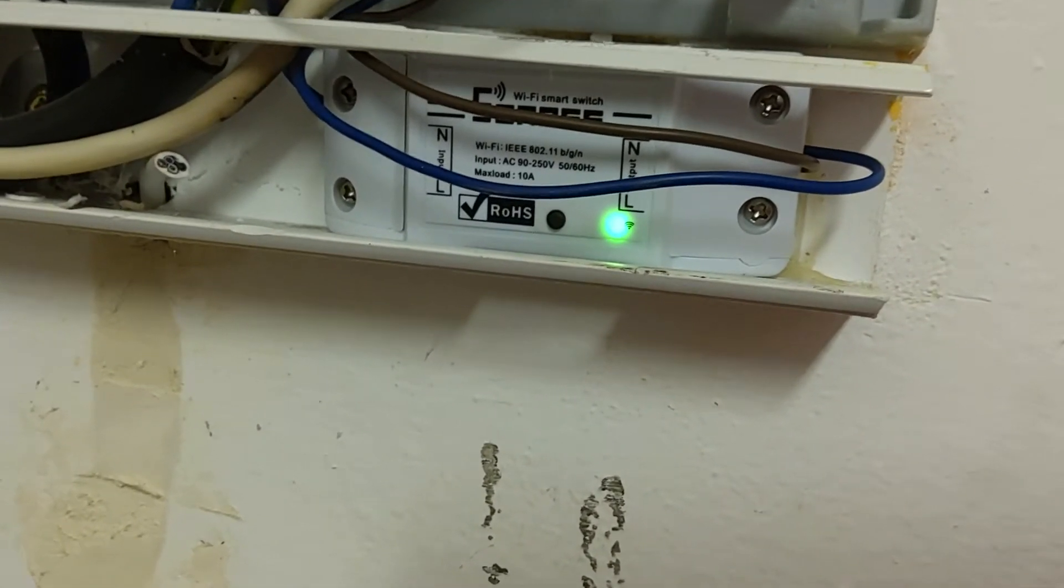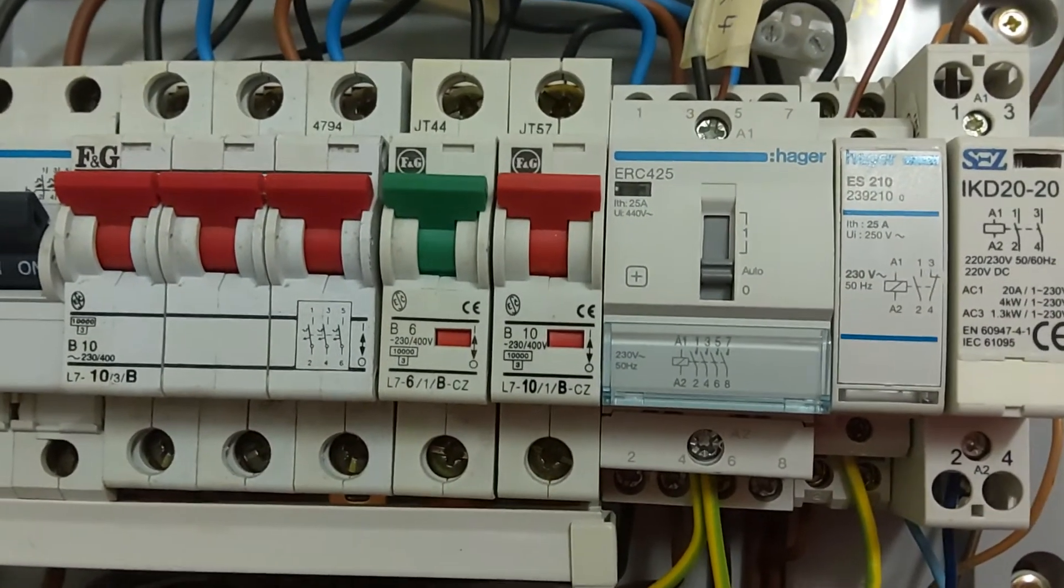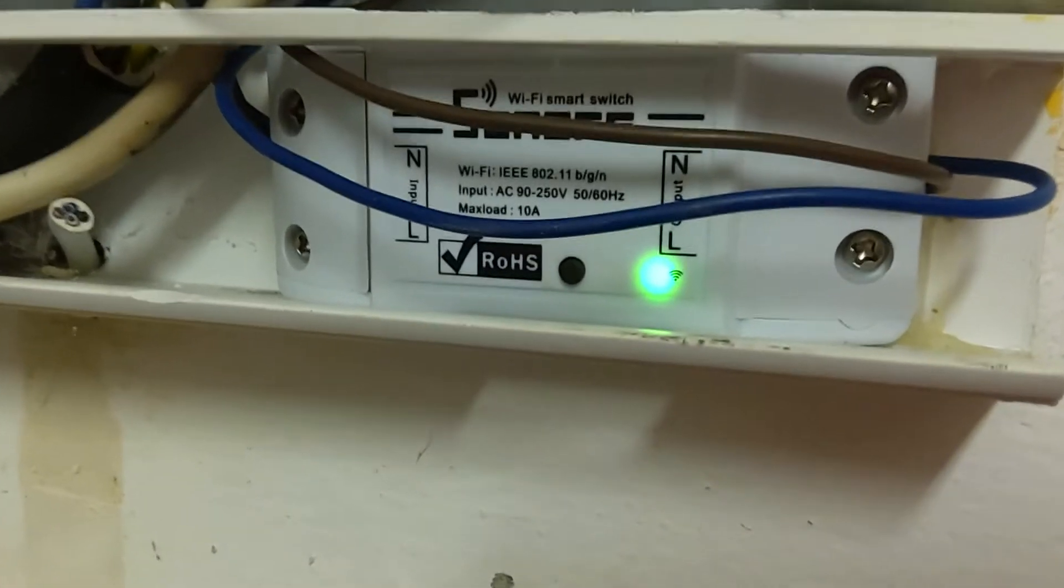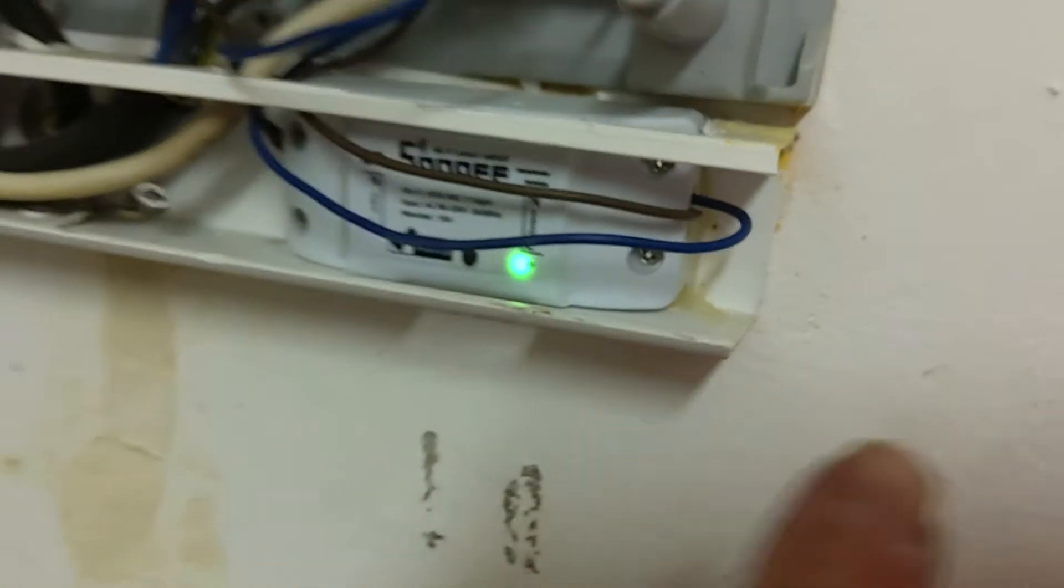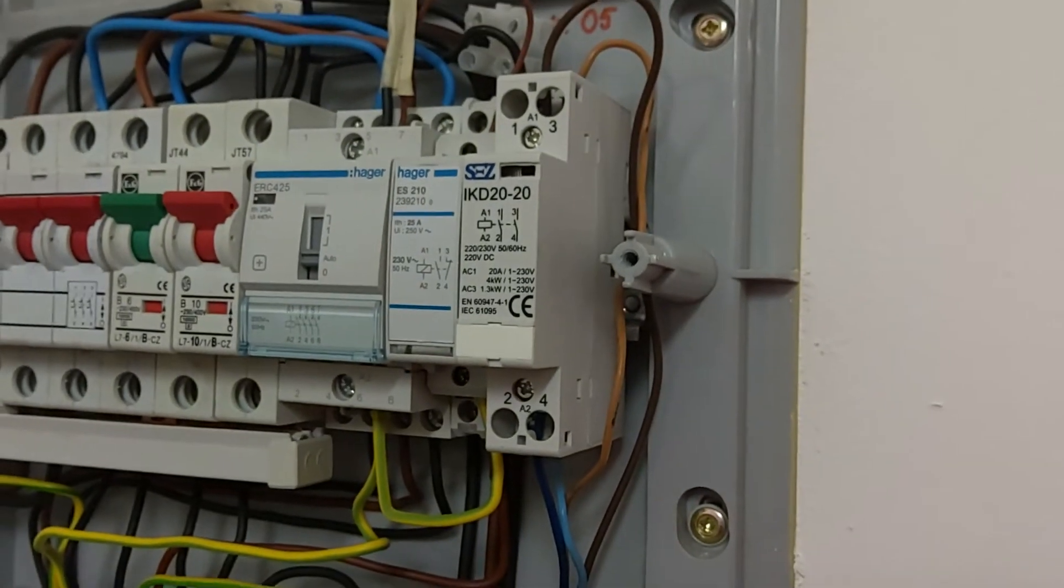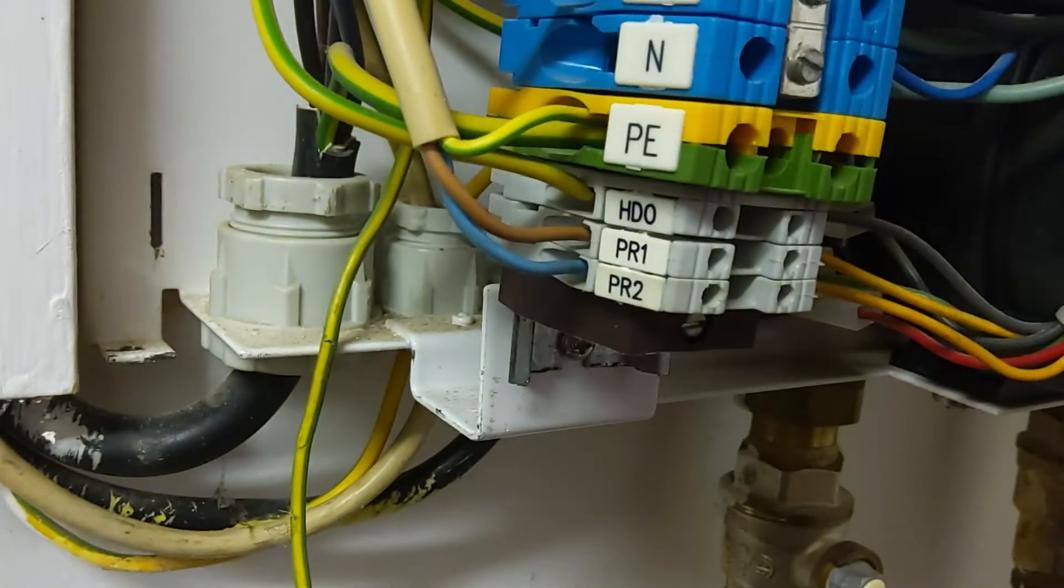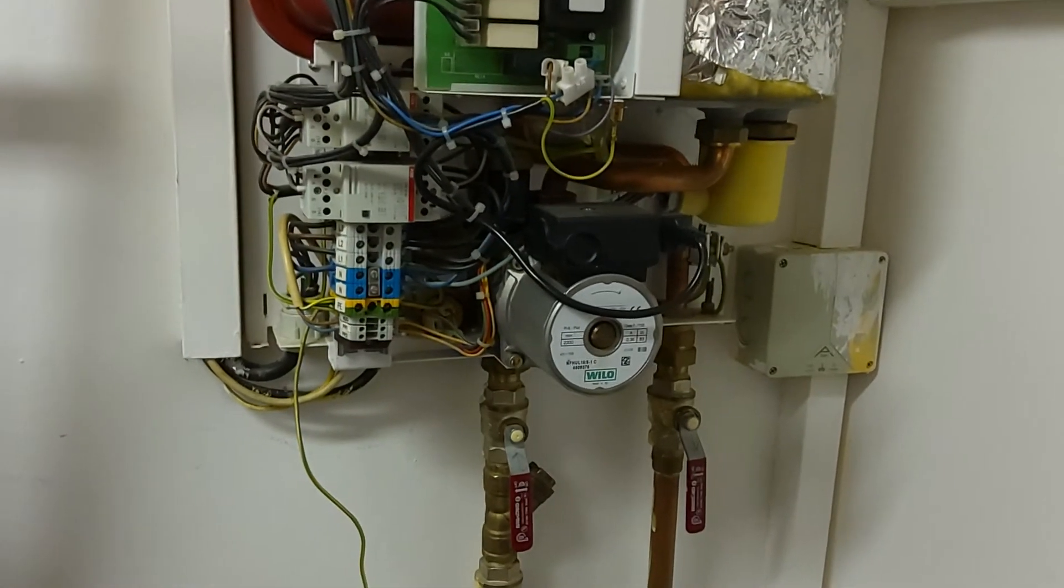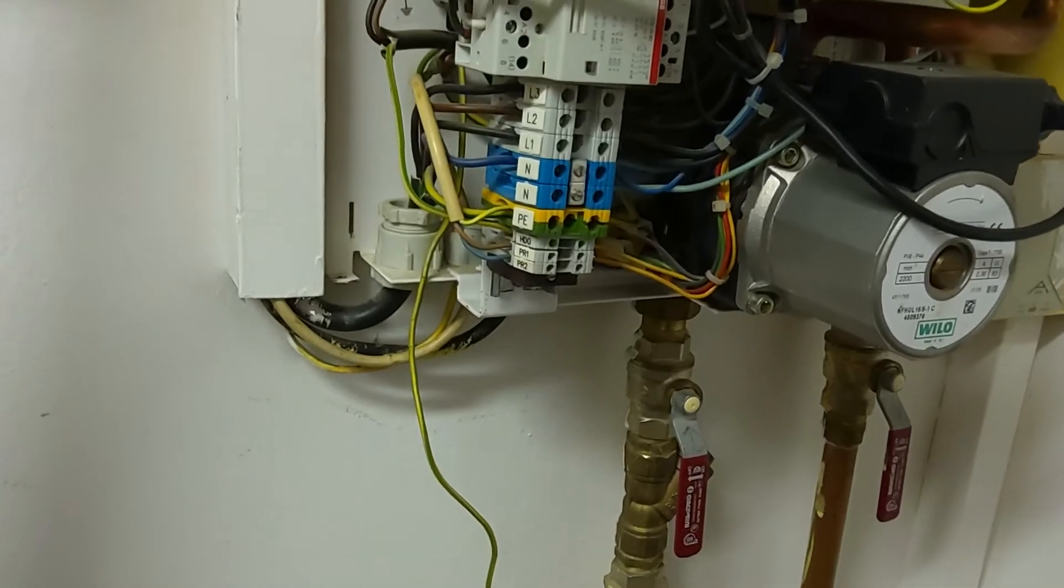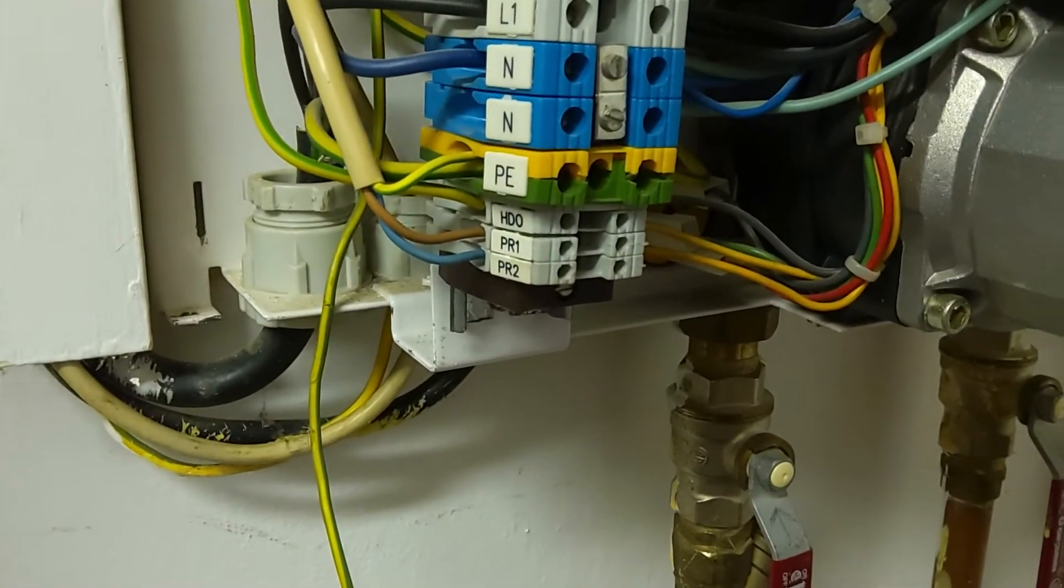I have taken a 6 amp feed to feed the switch, then the control side over here goes up to a contactor, and then the contactor feeds back down to PR1 and PR2. Now all boiler systems will have PR1, PR2, or similar named contacts.